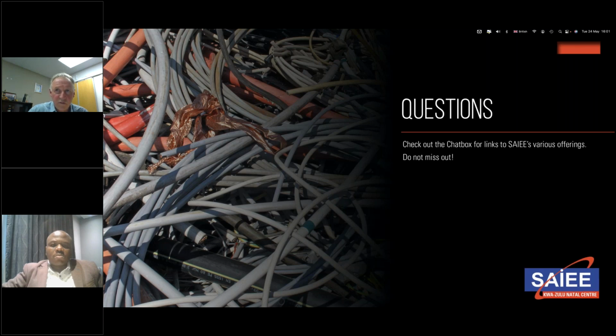So the IACS of oxygen-free copper can go up to about 103%. So it could make a 3% difference, just the oxygen. Copper and most metals are very susceptible to contaminants, and copper is a good conductor of electricity. So I would say it probably would not make a massive difference to the copper conductivity, but it's also, of course, quite an expensive metal, and one would have to see what the benefits are from doing that. So it might not have the benefit that one would think it might have.